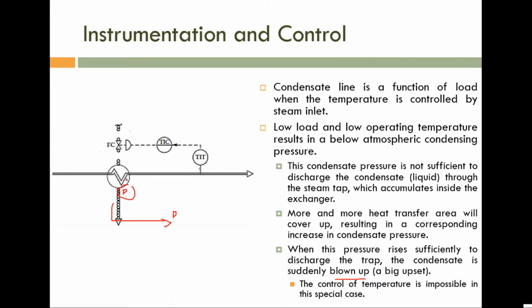So with the condensation, the liquid level will increase. With the increase of liquid, slowly the heat transfer area will decrease. So what is happening if the heat transfer area is decreased? Definitely the heat transfer will decrease. With the decrease of heat transfer, the condensation rate will decrease. That is one problem.